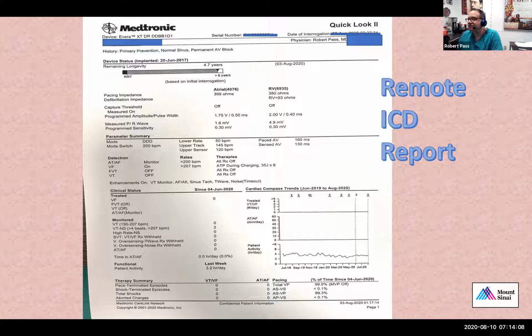So the pacing impedance is usually a measurement of the integrity of the insulation of the lead. When the lead insulation is injured, which is almost always a precursor to the lead failing, we will see marked changes either up or down depending on what the problem is. So what we like to see is that the pace impedance is not changing very much over time. And by not much, I would say usually within 50 to 100 ohms, it shouldn't really change from measurement to measurement. By seeing that the pace impedance is stable, we are indirectly knowing that the patient has stable leads, that nothing is happening in a bad way towards the leads.